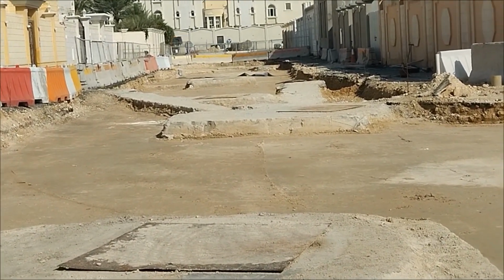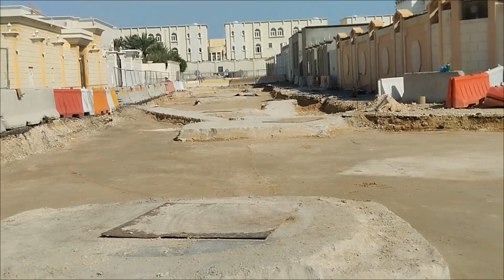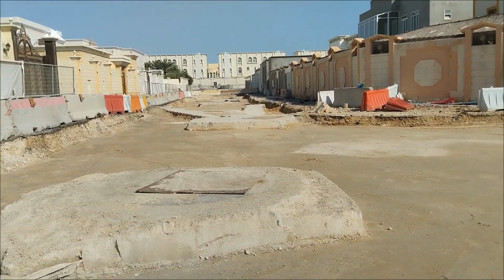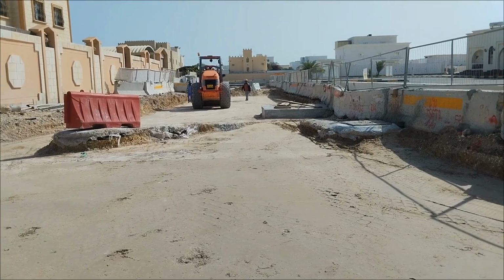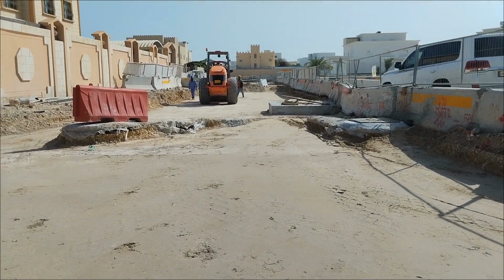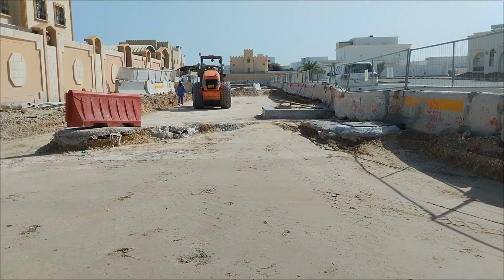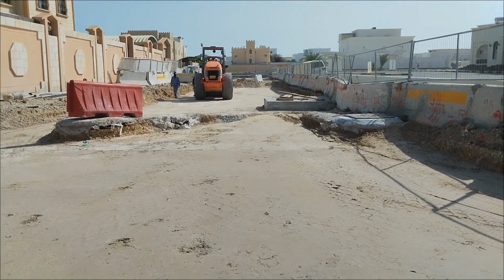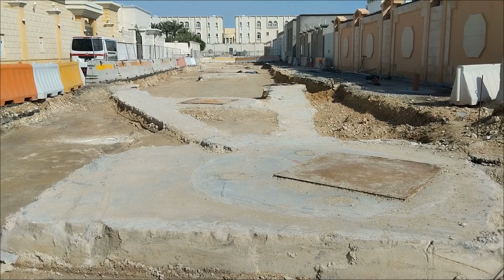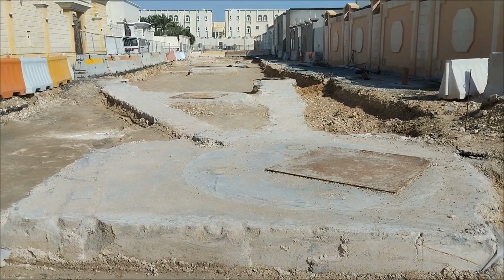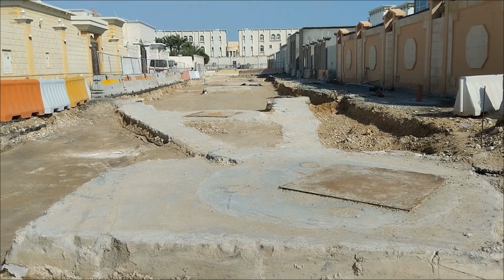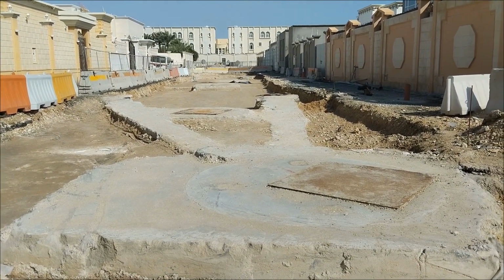The underground ducts and the gullies are shallow activities, so that's why they should be started after the deep excavation utilities have been completed, like foul sewer line, TC line, potable water line, surface water line. Once all these activities are completed, then the road crossing duct will be installed. As you can see here, all the road crossing ducts and gullies are completed. This is the manhole connection with the gullies.